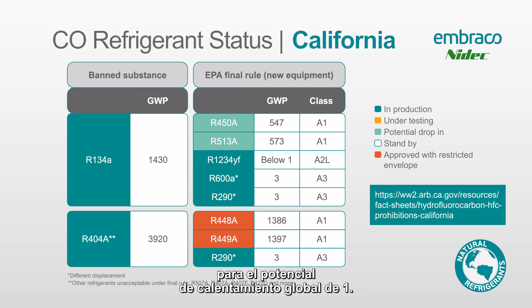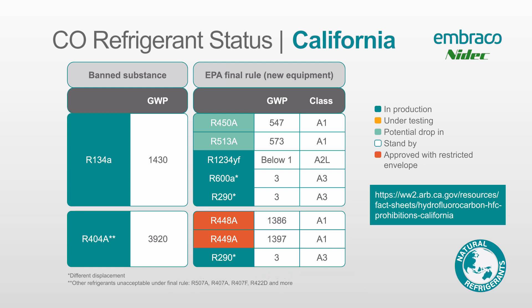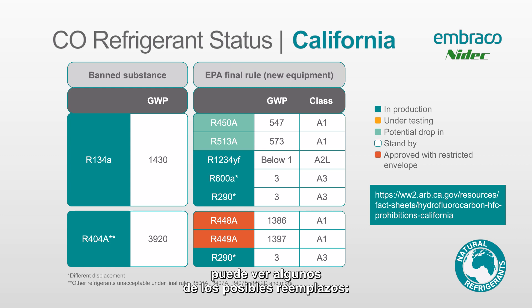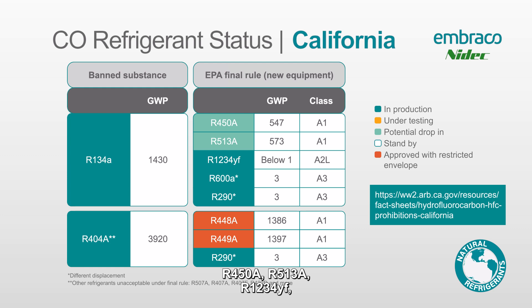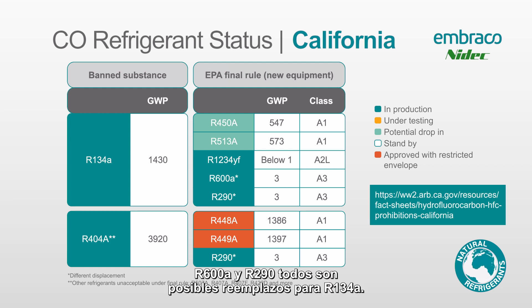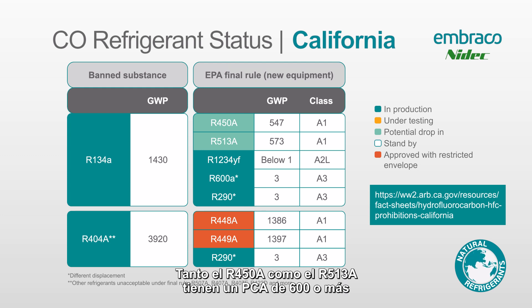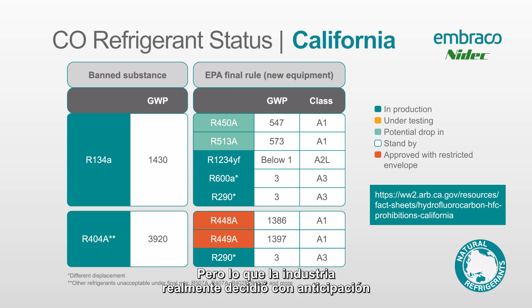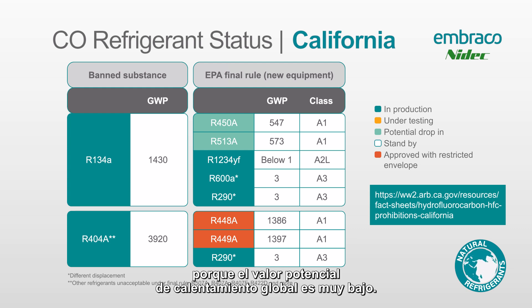CO2 is our baseline gas with a global warming potential of 1. So what the EPA decided to do originally, and then the states followed up and decided to do themselves, was to move to gases with a lower global warming potential. If you look at the right side of the chart, you can see some of the potential replacements: R450A, 513A, 1234YF, 600A, and R290 are all potential replacements for R134A. R450A and R513A both have a GWP at 600 or less, and we refer to them as interim gases — these will probably not be permanent as they'll end up being banned just as the others have. But where the industry really decided to head was to look at gases like R600A and R290 because the global warming potential value is so low.